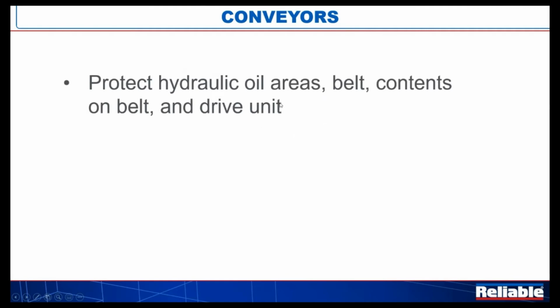Conveyors. We need to protect all the hydraulic oil areas. We need to protect the belt. And when you think in terms of the belt, remember you've got the belt on the top with the material on it. At some point at the end, it does a 180-degree turn and comes back underneath itself. So when they say to protect the belt, they mean both the top and the bottom. Both NFPA 15 and Factory Mutual 4-1N will give you some really nice pictures, or some guidelines, I should say, on how to accomplish that. Obviously, the contents on the belt, and then whatever drive units are driving the belt.